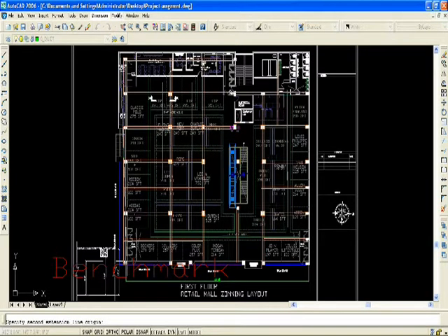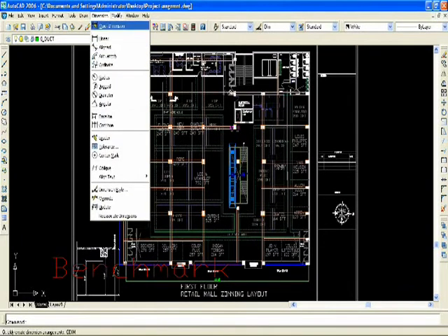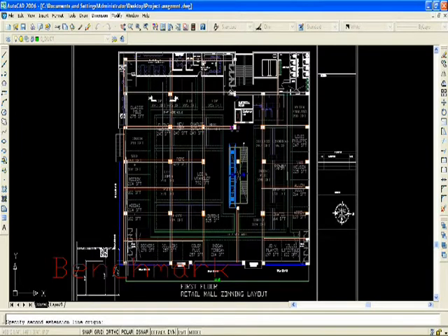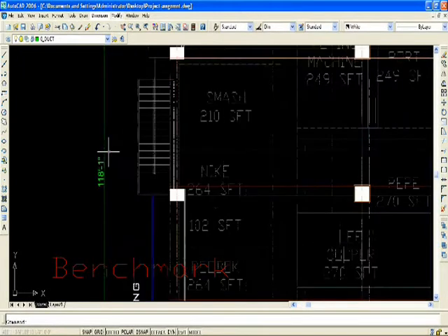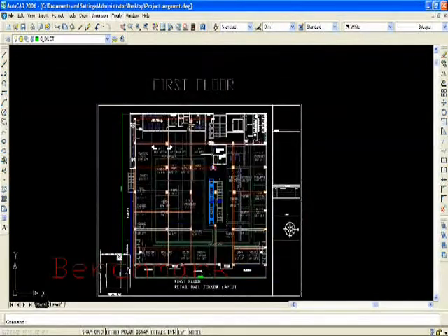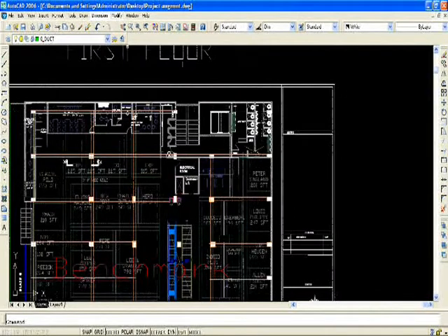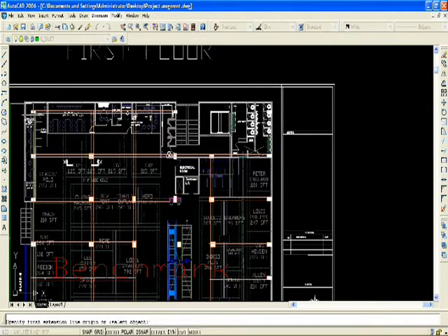Whenever we do any cooling calculation, we must have all the length, width, and height for feeding this data into our software. You can use any software to measure this data, or you can do it with a hard copy also. This is a Mumbai based project, so we are going to use weather data for outside conditions and ISHRAE standards for ventilation. We are considering 5 CFM per person. This is only a general comfort application, so we are not going to consider it as a LEED or any high performance building. We use it only for the normal application. We must have this data before feeding into our software.